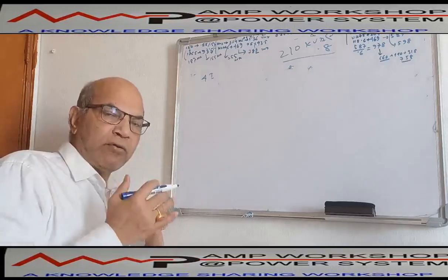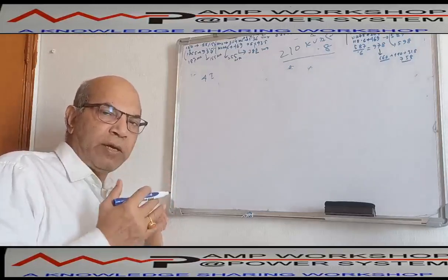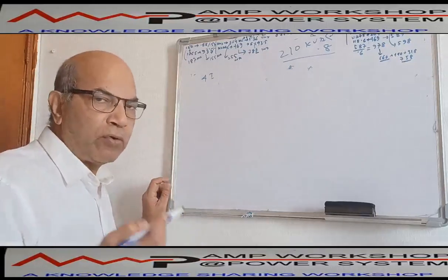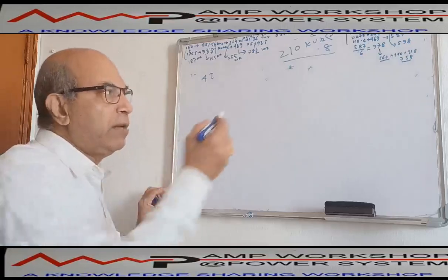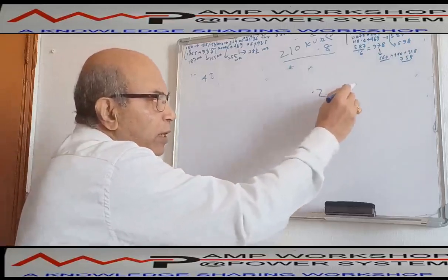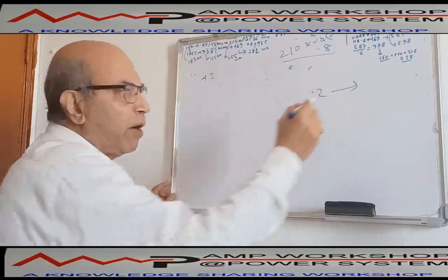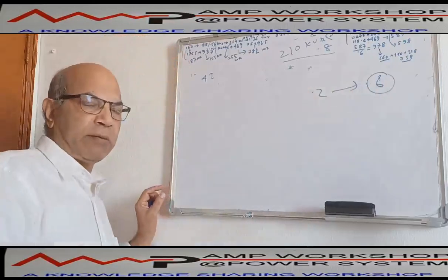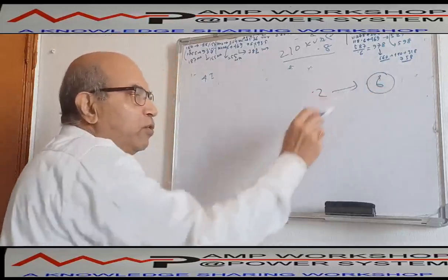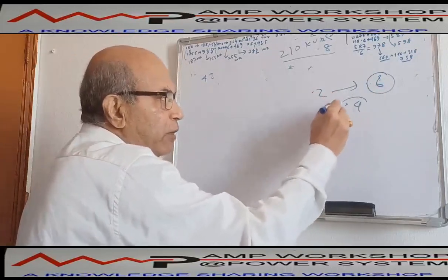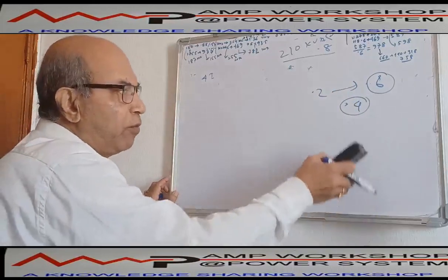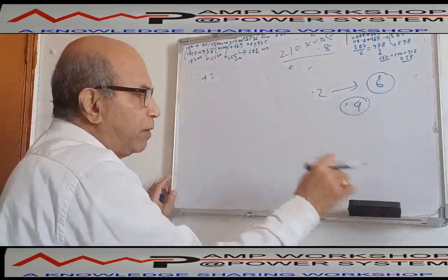the reactive current will gradually reduce, or kVAR will reduce, and active kilowatt will increase. So in the initial phase of the motor the power factor is very poor. It may be in the range of 0.2, but when it goes to full speed, the power factor may go up to 0.6 or 0.7 at no load condition.